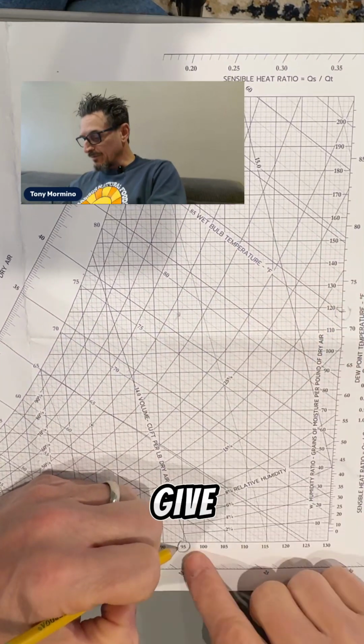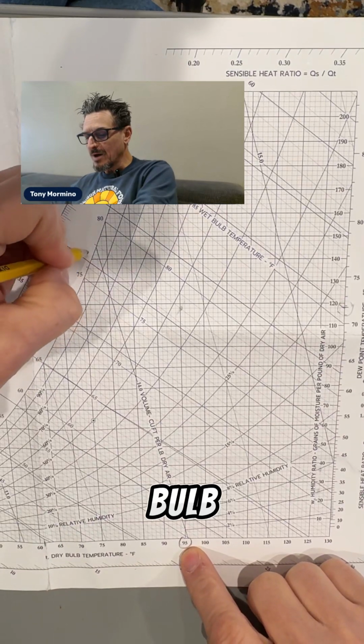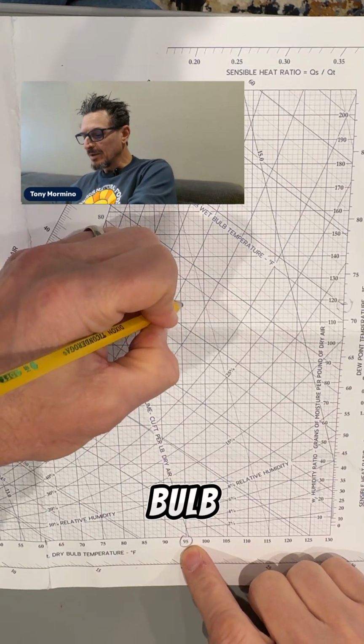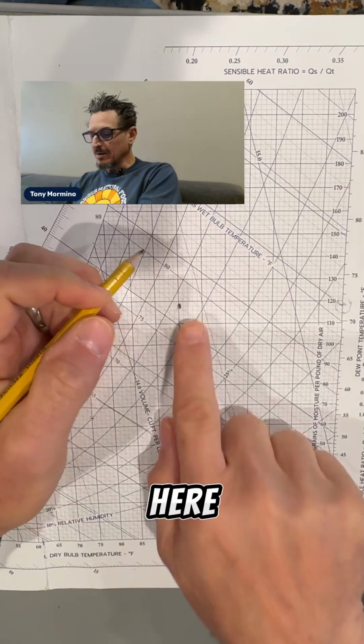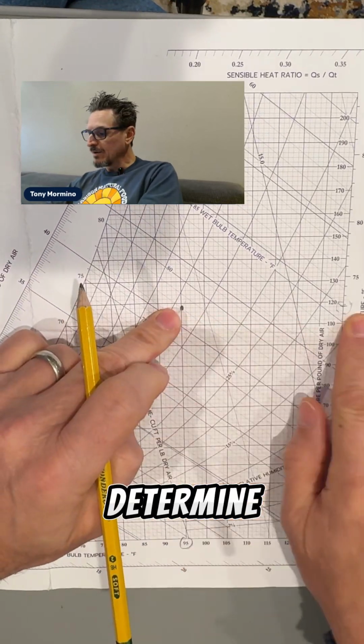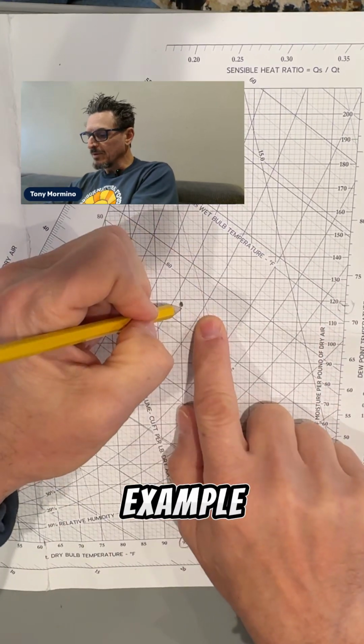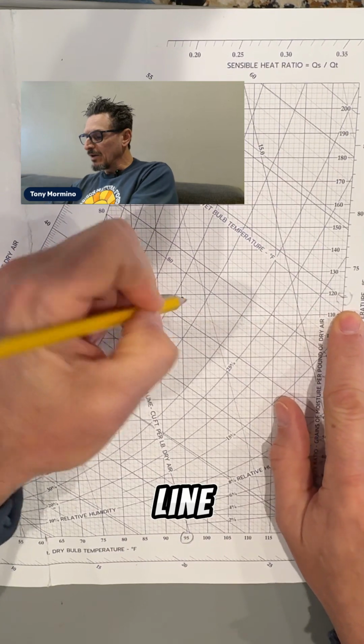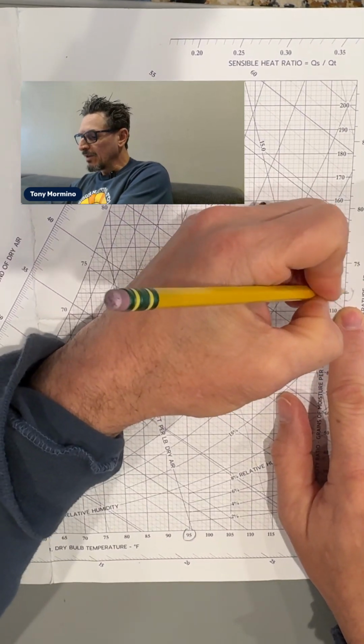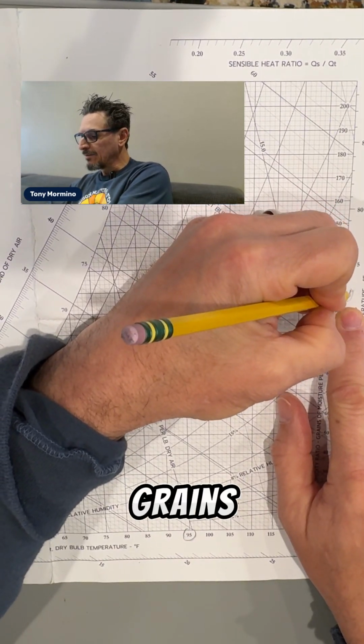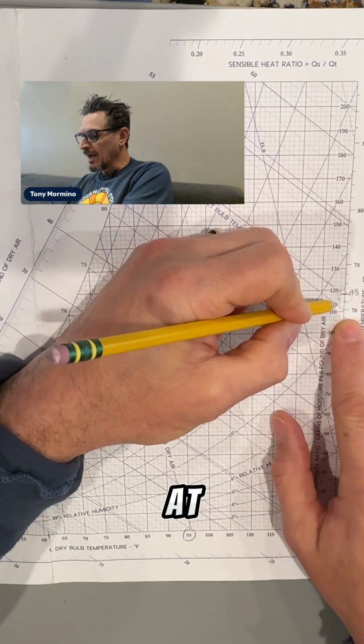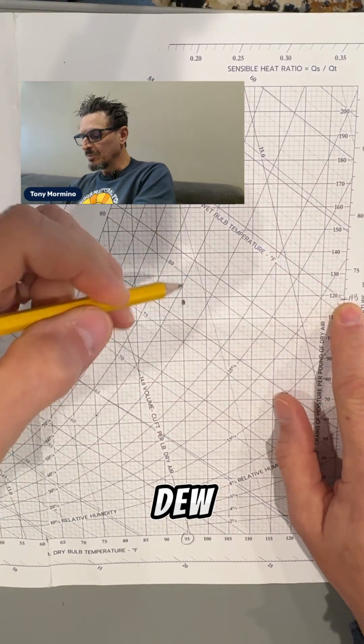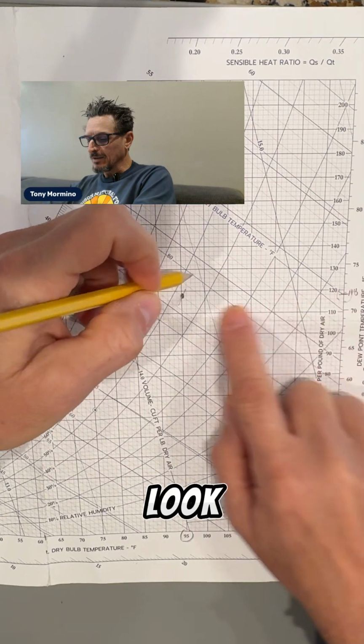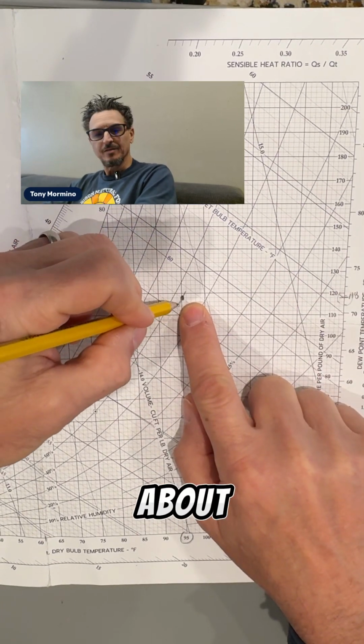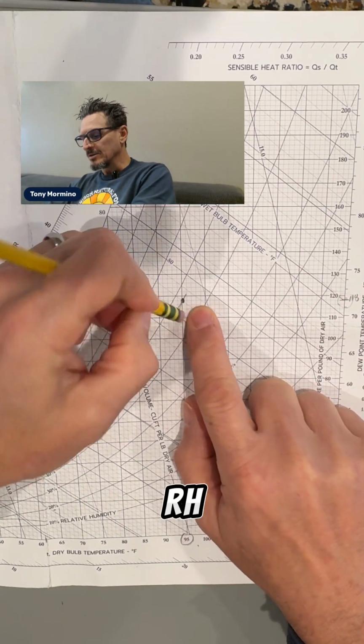Now, I'm going to give an example of 95-degree dry bulb, 78 wet bulb. If you plot that point here, you can determine any of the other points. So, for example, if I draw a straight line over to the edge here, you're looking at about 118 grains. You're looking at about 72-degree dew point. And if I look at the RH lines here, you're looking at about 58% RH.